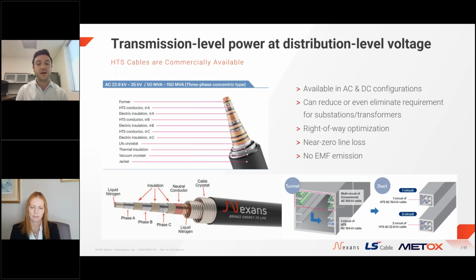We've highlighted the cable products from two of the suppliers of superconducting cables, both LS Cable and Nexans. You'll notice in these designs they've got 3-phase concentric designs, with all 3 phases in a single cable. This enables reduction of land needed to lay cables, as well as optimization of right-of-way. These cables, due to superconductivity, have near zero line loss and also don't have any EMF emission.